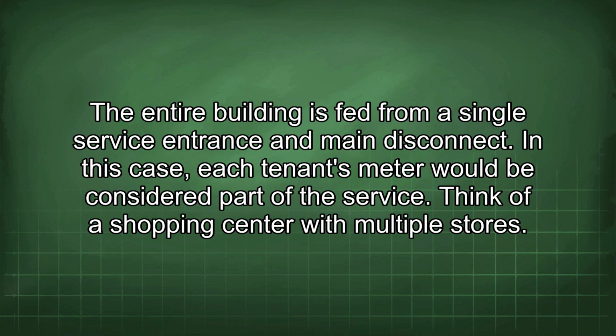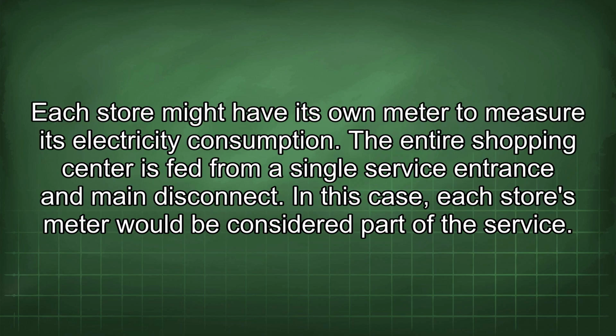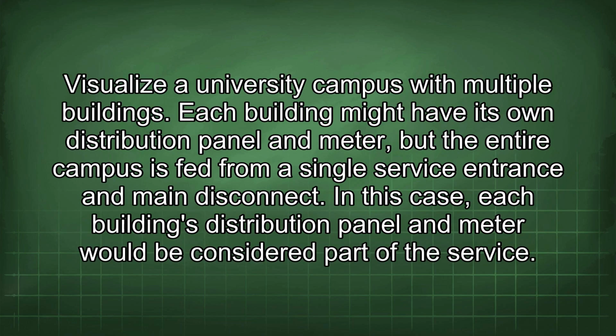Think of a shopping center with multiple stores. Each store might have its own meter to measure its electricity consumption. The entire shopping center is fed from a single service entrance and main disconnect. In this case, each store's meter would be considered part of the service. Visualize a university campus with multiple buildings. Each building might have its own distribution panel and meter, but the entire campus is fed from a single service entrance and main disconnect. In this case, each building's distribution panel and meter would be considered part of the service.